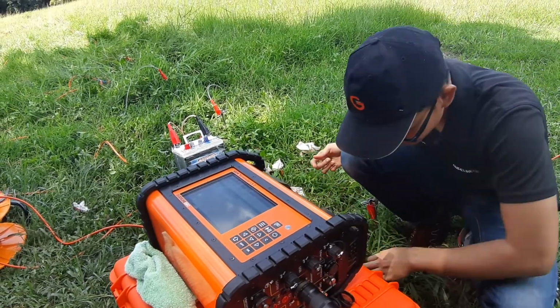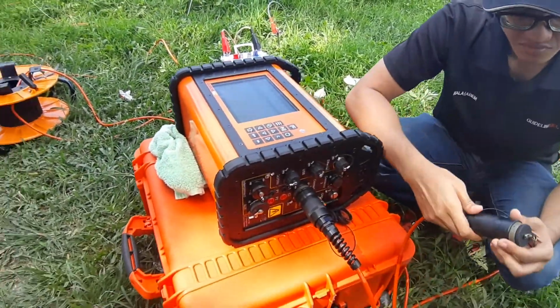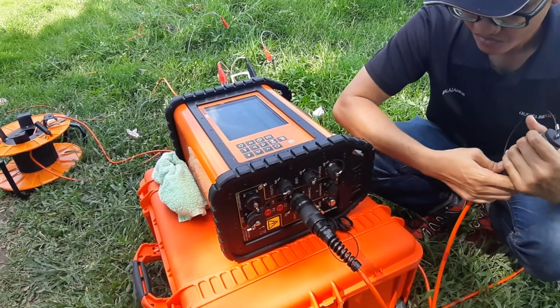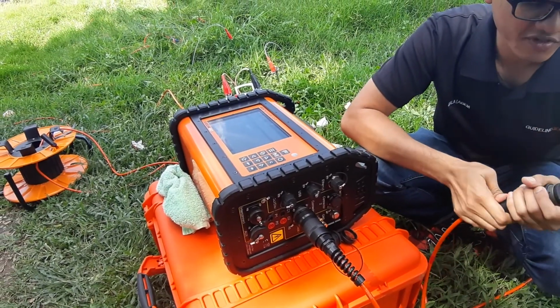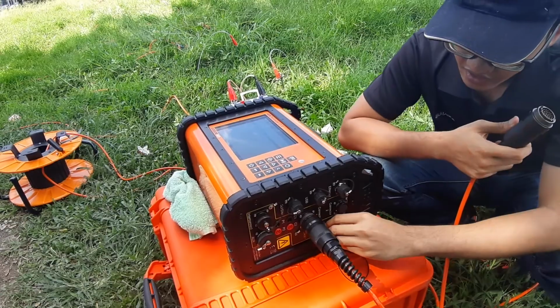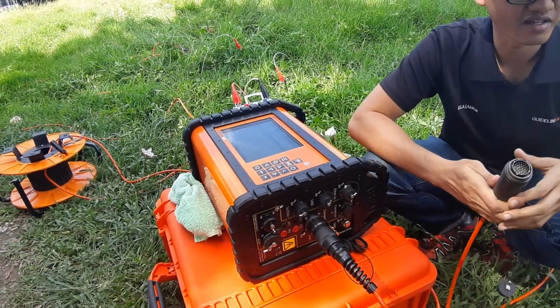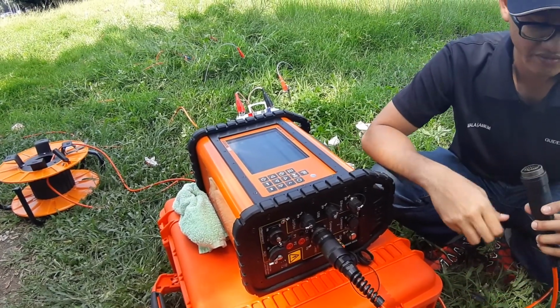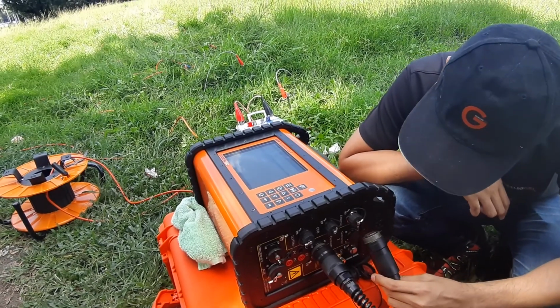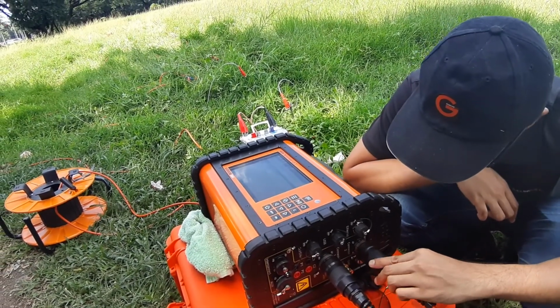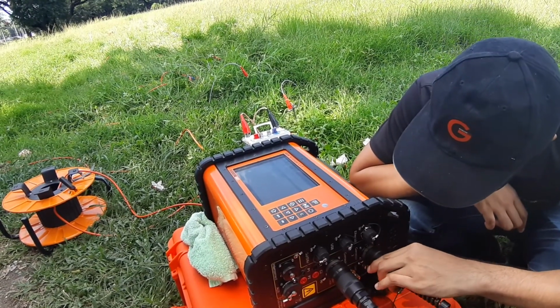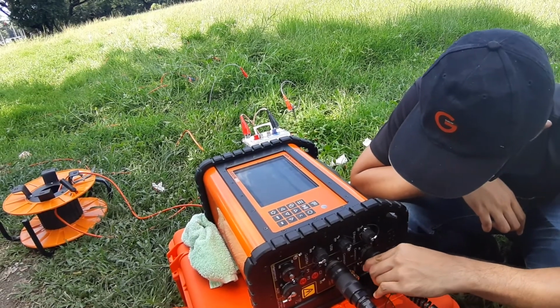Okay, so what about the ground? Is it really necessary to put a grounding cable there? No. Yeah, for safety purposes you can put a grounding, like put some cables, and you have electrodes, but usually, not really. You don't usually do that.